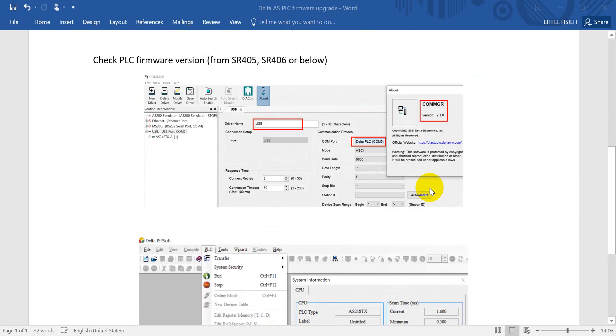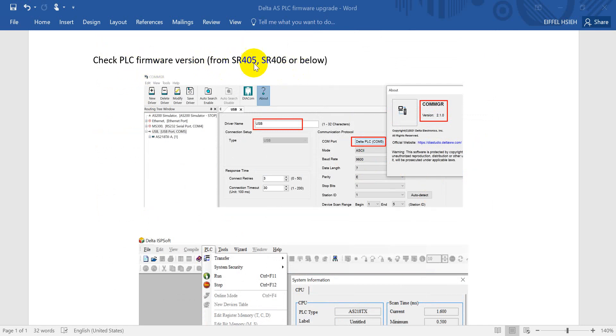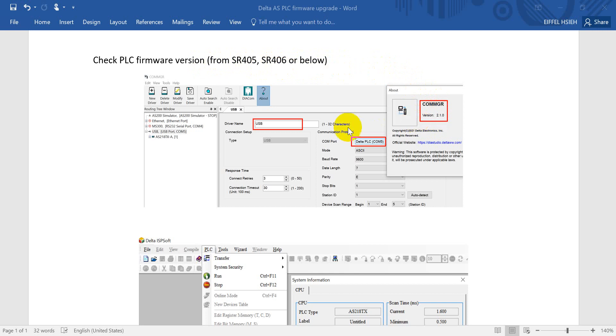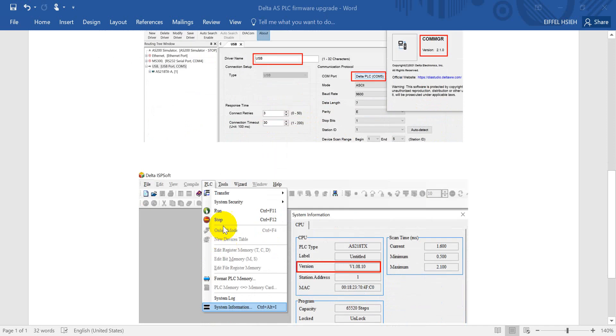Okay, then here I will show you how to check a Delta AS PLC firmware version. So we provide two methods. First, you can check from special register 405 or 406. Or you can try the below method. We use the command manager to establish the connection. Then we can check the system information and we can get the firmware.